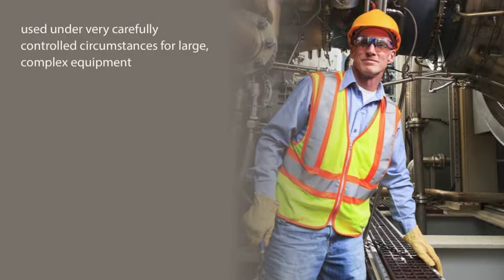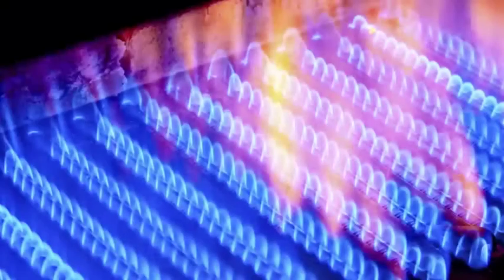These systems are generally used under very carefully controlled circumstances for large, complex equipment that might start only once every 5 to 10 years. This could be refinery equipment, glass melting equipment, and/or equipment used in large paper mills that run for very long periods. Risks are controlled with extensive startup procedures and well-trained personnel. In some cases, this is done in conjunction with specialized contractors that have temporary heat-up equipment.